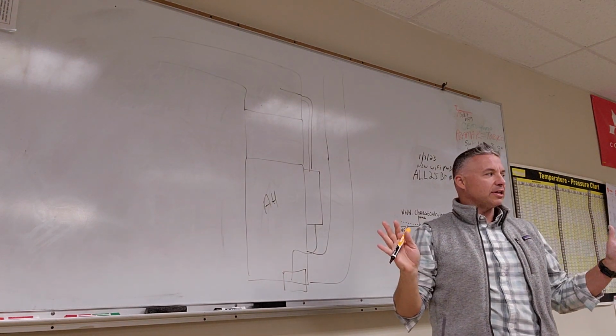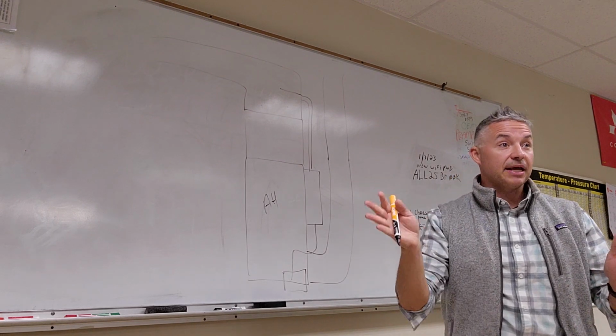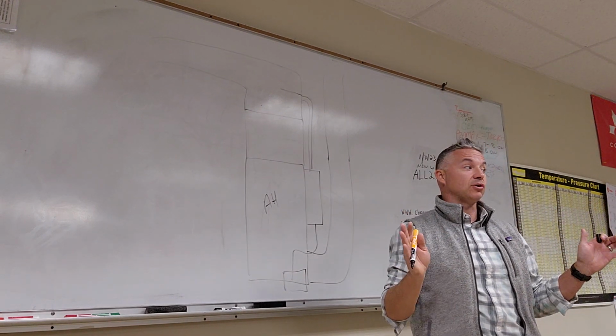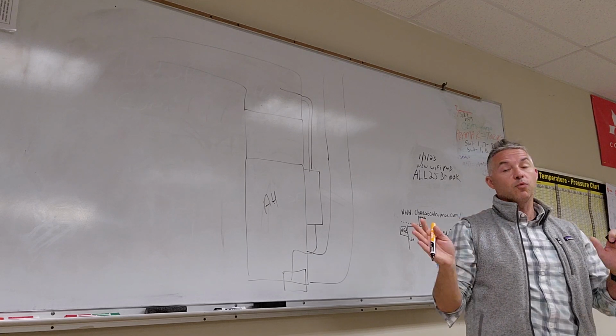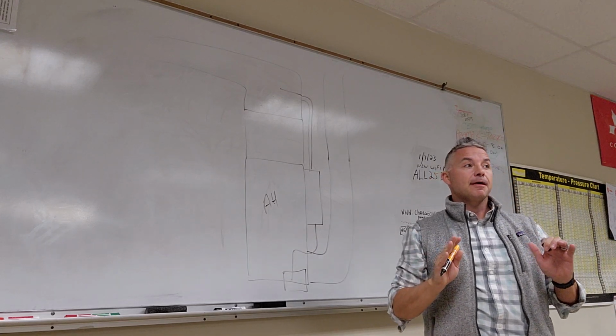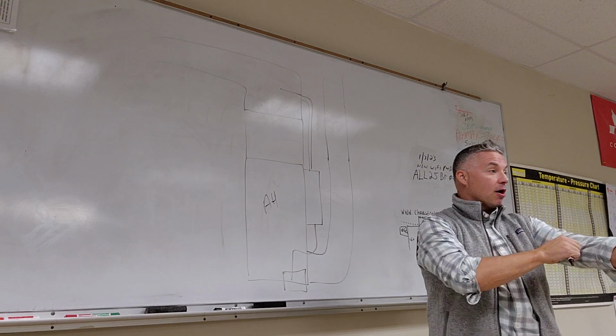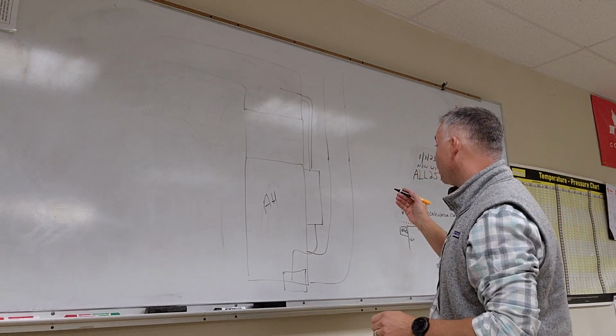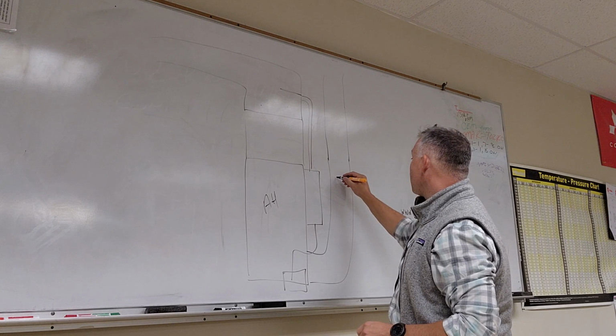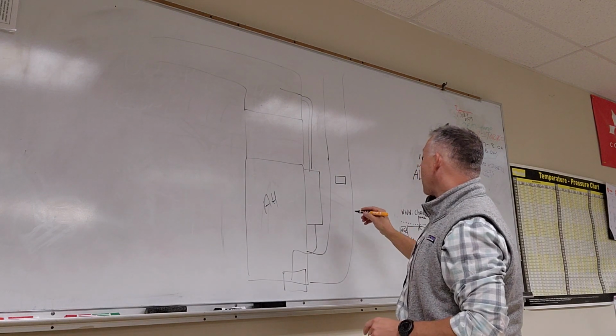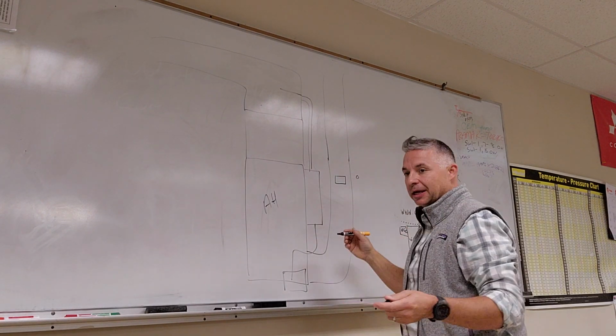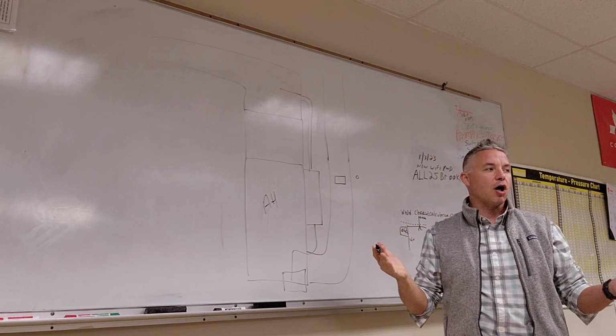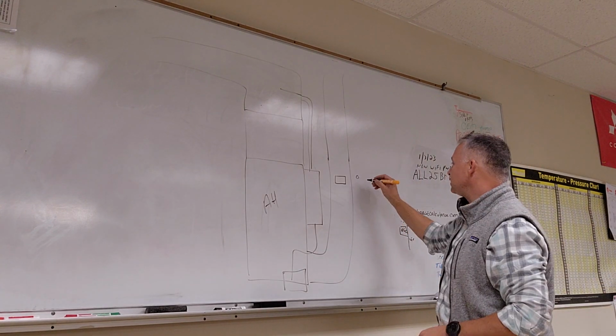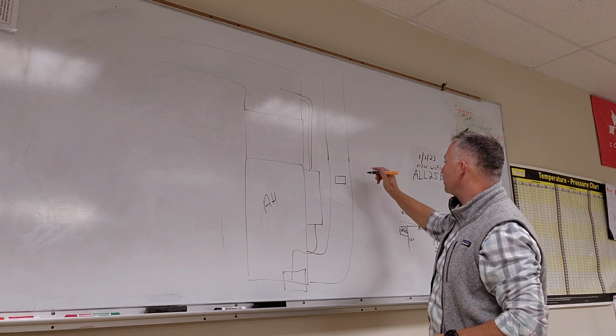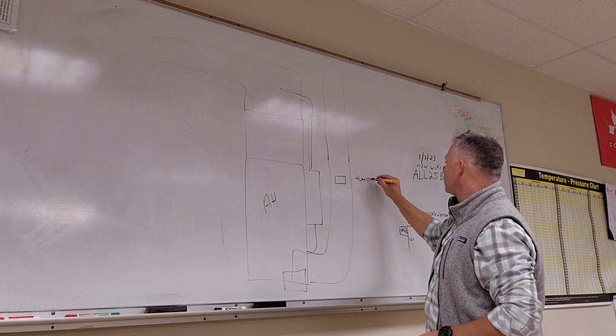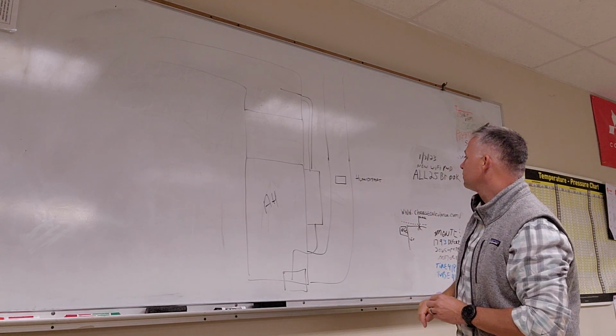It's going to vary on almost every job. You'll see some jobs that are all installed the same way, and then you'll see little variances in all the different jobs as far as where we put these controls and what the operating limits are and so on and so forth. But the components that you're going to see most often is an operating humidistat, right? A low limit. There's a bunch of different things to call it. It's a humidistat. And basically we'll just call it humidistat. Yeah, low, I see what you're saying, a low limit and high limit.